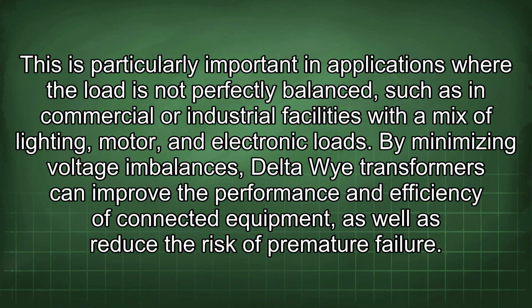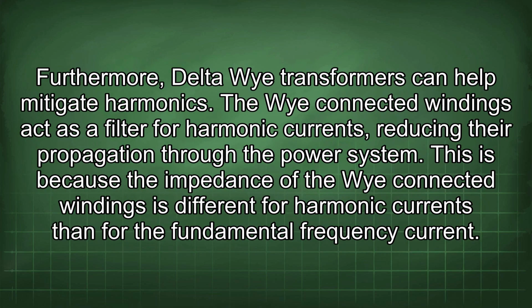By minimizing voltage imbalances, Delta Wye transformers can improve the performance and efficiency of connected equipment, as well as reduce the risk of premature failure. Furthermore, Delta Wye transformers can help mitigate harmonics. The Y-connected windings act as a filter for harmonic currents, reducing their propagation through the power system. This is because the impedance of the Y-connected windings is different for harmonic currents than for the fundamental frequency current.